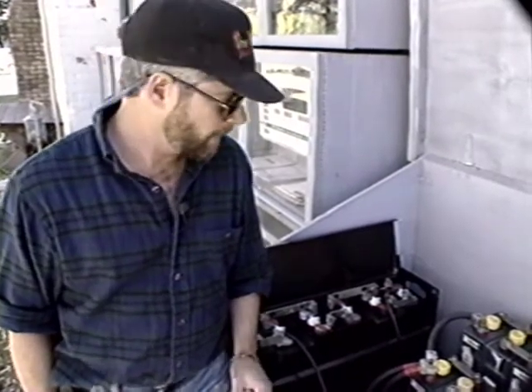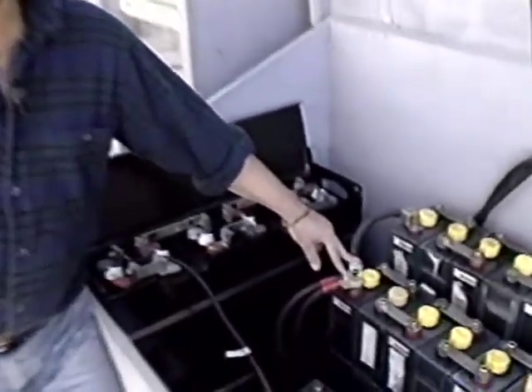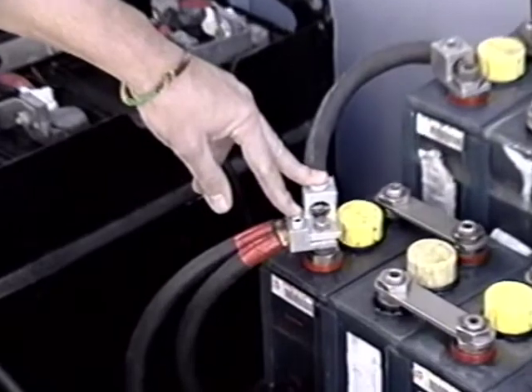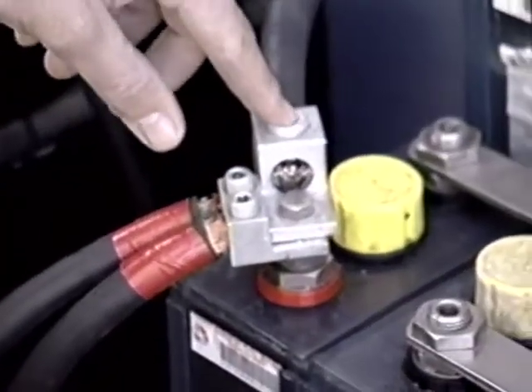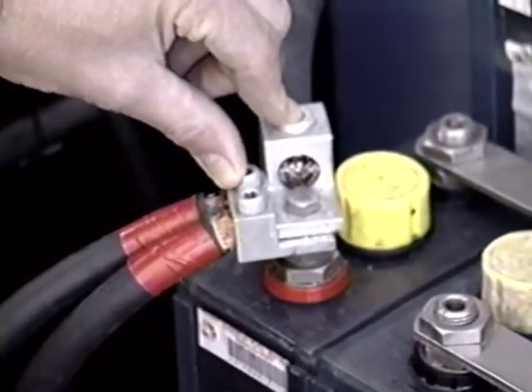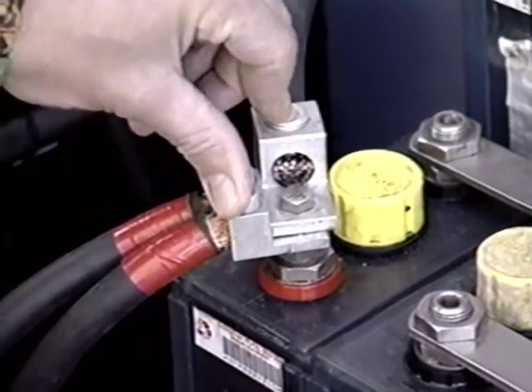There are three basic things to remember when trying to maintain any type of battery bank. The first one is to keep tight connections. Tight connections allow for good conductivity of the electrons through the wires. We don't want to have resistance. We want low resistance connections, therefore tight connections.